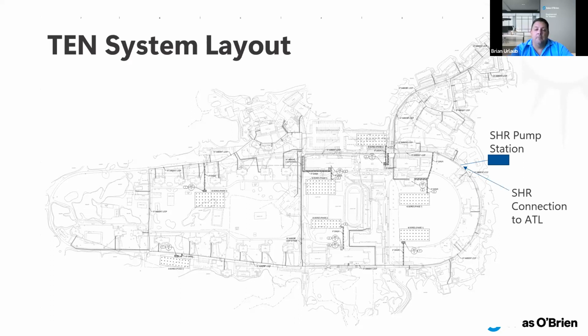These are distributed heat pumps in all these buildings, no central plant here. We also looked at how all these buildings have an outflow point on site with their effluent, so we gave them an option to reduce the bore field by putting in a sewage heat recovery station on the main line leaving the site. We can inject that back into this ambient temperature loop, and we could remove almost this entire bore field by adding this station, though we'd have to move a couple of connection points around. This is another single-pipe ambient temperature loop application.